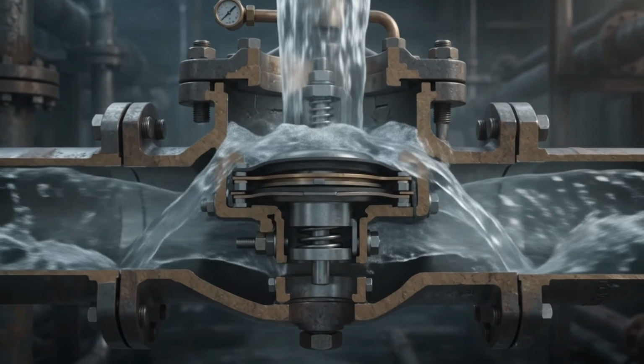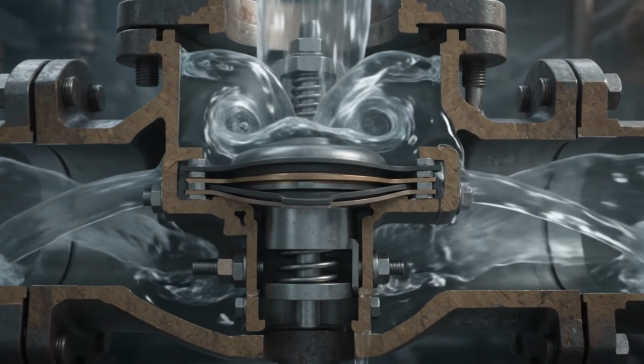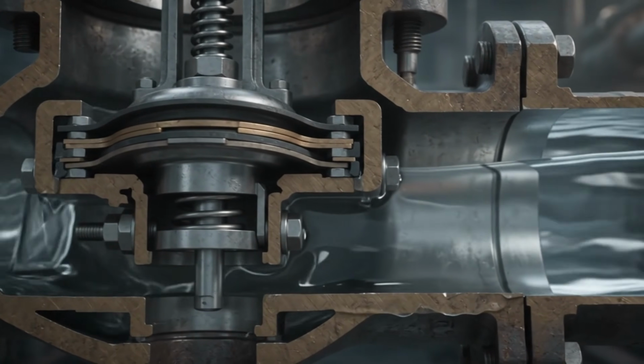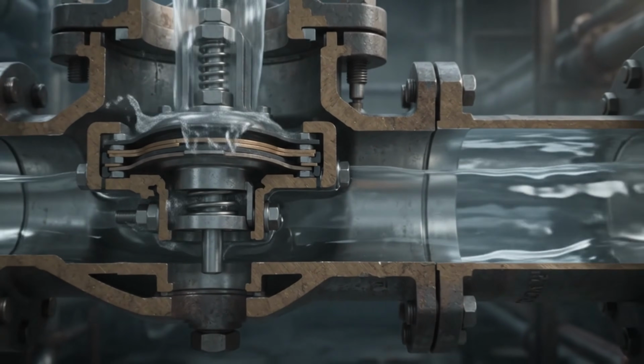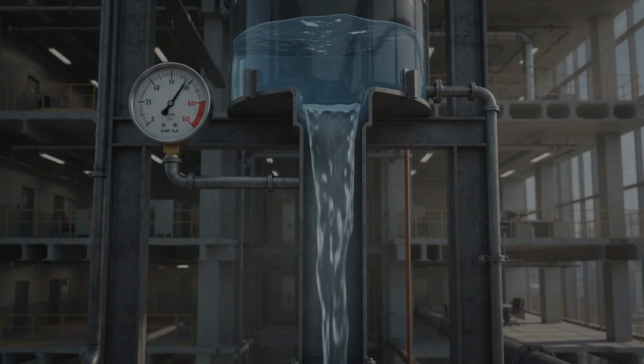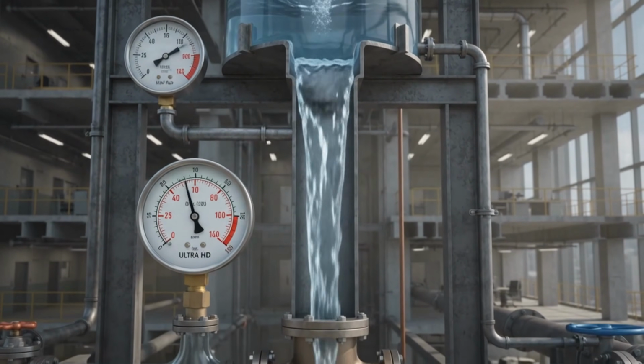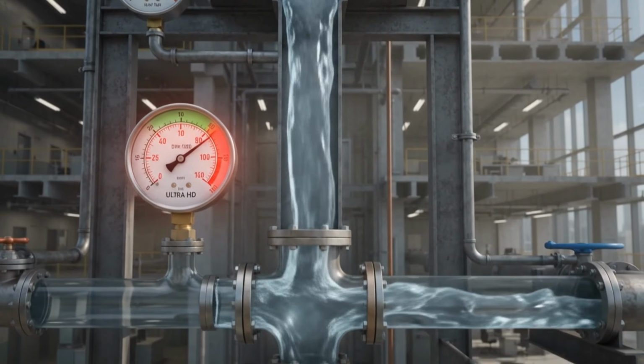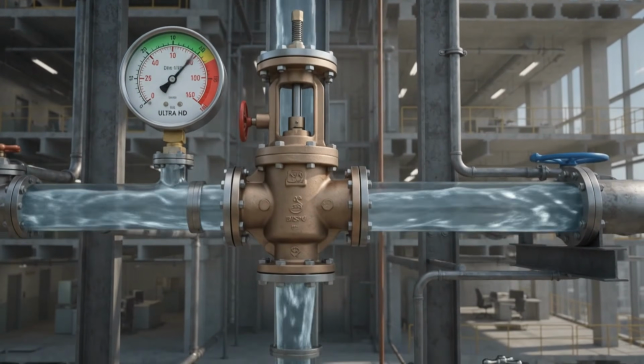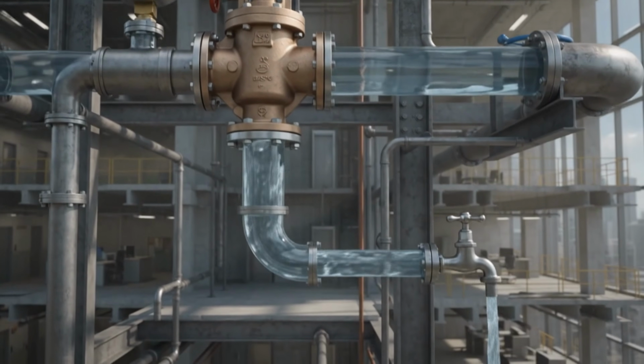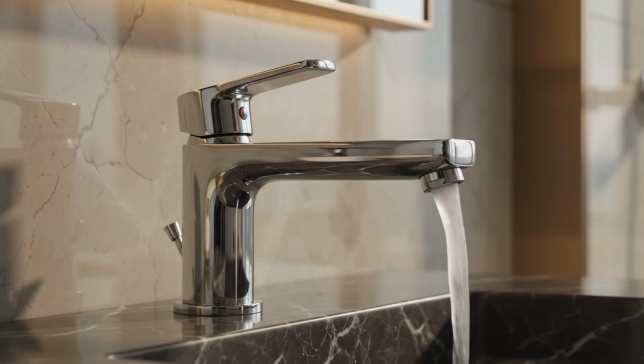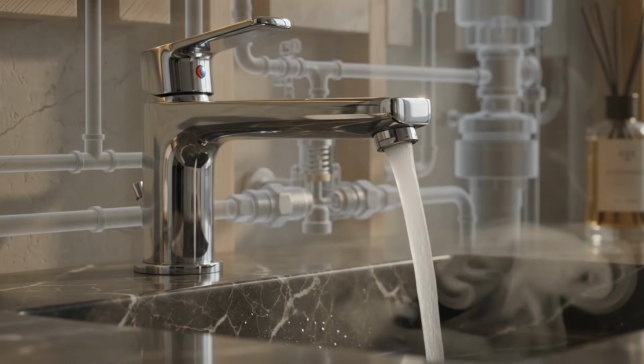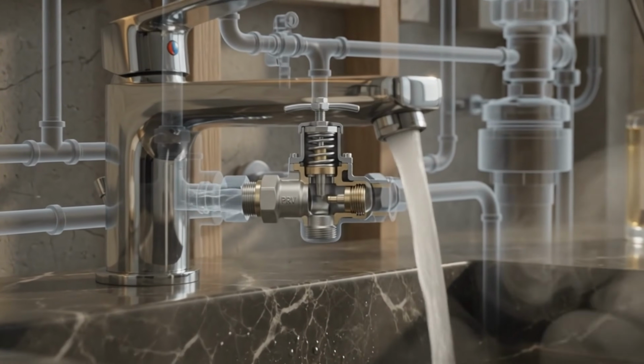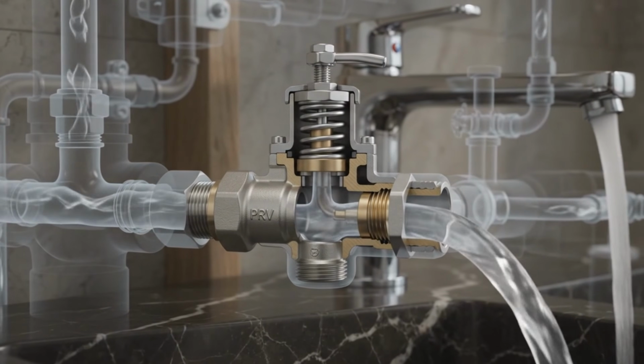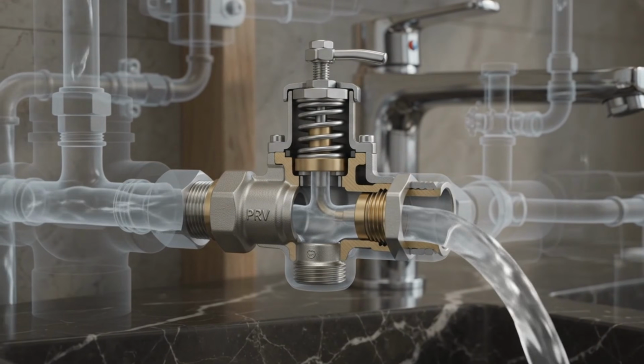Pressure-reducing valves, PRVs, are placed throughout the distribution network, automatically throttling water pressure to safe, consistent levels before it reaches any fixture. Without pressure-reducing valves, gravity alone would build dangerous pressure in any downfeed pipe, turning a simple tap into a hazardous high-pressure jet capable of damage. Whether you're on the 5th floor or the 155th, pressure at your faucet is virtually identical, because PRVs normalize pressure across every zone and every level.